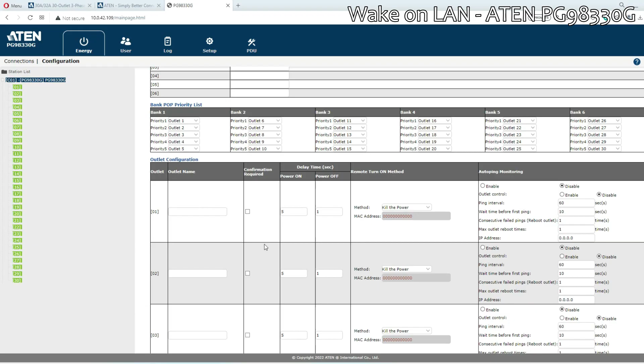Now, if we go to the configuration, we have more options on how to turn off and turn on the power. For instance, as a simple way on socket number 2, which shuts down one of our displays, we have the method of killing the power when I want to shut down. However, when I want to put the power back, if it is a server with Wake on LAN enabled, the simple fact that I put power behind the server doesn't mean the server will start. The server will still stay shut down. It will be aware because of its Wake on LAN capabilities, but it will not start.